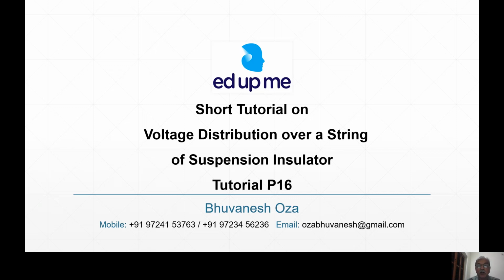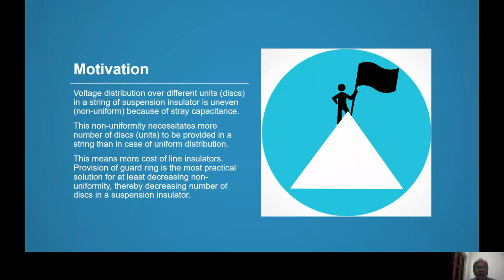The trouble is, because of this uneven voltage distribution, we need a higher number of insulators than in the case of uniform distribution. But uniform distribution is not there naturally. Therefore, we need a higher number of insulators, and therefore the cost of insulation increases, the cost of transmission increases. And therefore, to study this uneven voltage distribution is very interesting.